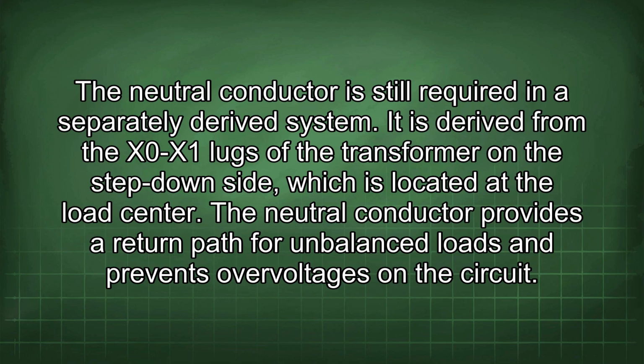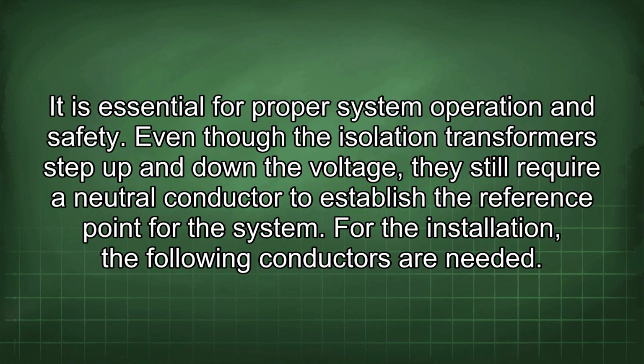It is derived from the X0-X1 lugs of the transformer on the step-down side, which is located at the load center. The neutral conductor provides a return path for unbalanced loads and prevents overvoltages on the circuit. It is essential for proper system operation and safety. Even though the isolation transformers step up and down the voltage, they still require a neutral conductor to establish the reference point for the system.